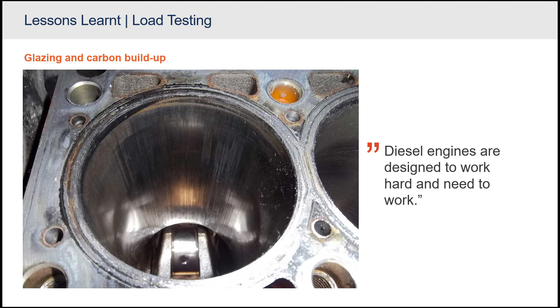So the key switch, specifically for the reason of this glazing and making sure we run it under load - we often see bad practices out there where clients start their generators with good intent once a week with no load, run it to make sure it runs fine, and think they're increasing reliability. But remember, if you start it without load, you're running it without load, which results in exactly the carbon buildup we mentioned, which is bad for the generator.